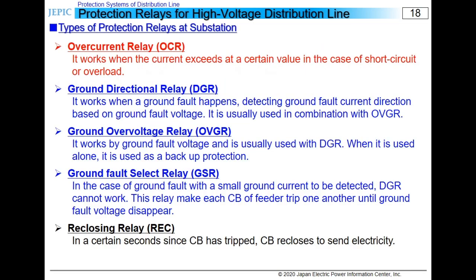From this slide, I'll explain how protection relays in substations work. Here, I'll explain about the types of protection relays in substations. Overcurrent relay is a relay for overload or short circuit. This relay has two CTs, which is installed to every feeder and usually monitored two phases of the three.